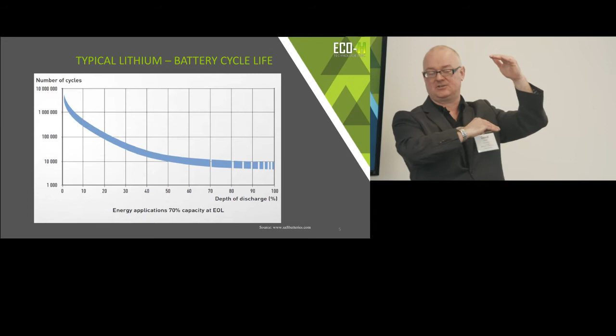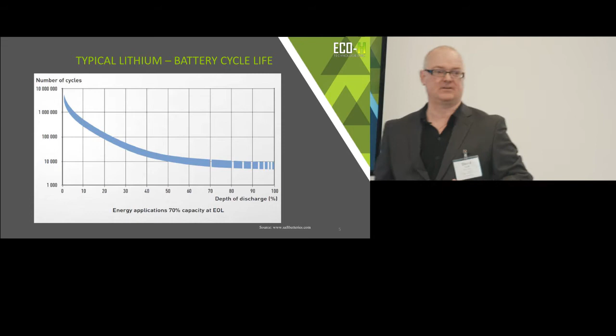The chances of people discharging from 100% to zero and back every day is zero. Everyone has a charger at the office, in the car, or at home. So if you only discharge to 50% and back to full, you've used half the cycle. Logarithmically, you've gone from 300 cycles to 3,000 cycles. If you discharge at 25%, that 3,000 becomes 30,000 cycles. At 12.5%, you've now got 300,000 cycles. So how you use the energy storage, the energy component rather than the power component, will dictate how many cycles you have, and that dictates the life cycle of the system itself.